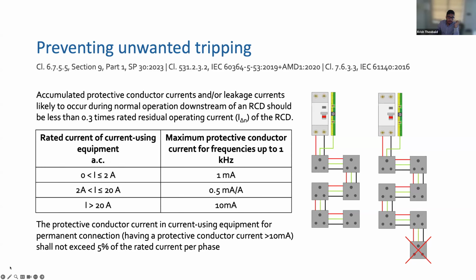Now, there are certain exceptions where for fixed equipment you can have an excess of 10 milliampere, but this shall not exceed 5% of the rated current per phase. On paper, this is a requirement. So is it followed in India by all equipment manufacturers?